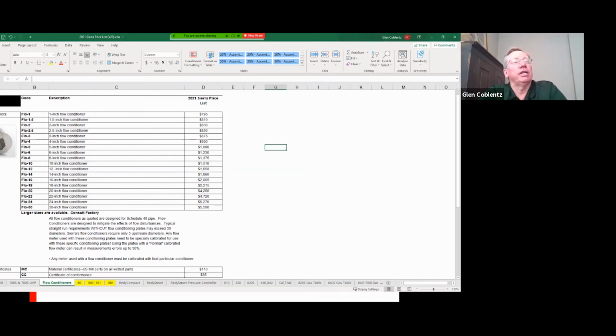A nice alternative to this is say, hey, on your 30-inch pipe, why don't you put a $5,500 flow plate in, tack weld it into place so you don't have to buy a 30-inch flange, and put a 640i downstream of it, 1 diameter downstream of it. We're giving you standard accuracy. It's a make your own 780i in a 30-inch pipe. You can plumb a 90 right into that. So your 5,500 here, let's call it 6,000 for the 640i, your $12,000 max. A 4-point multi-point from Kerrs or FCI, you're pushing $25,000. So you're half price already, and you're giving them an accurate measurement.